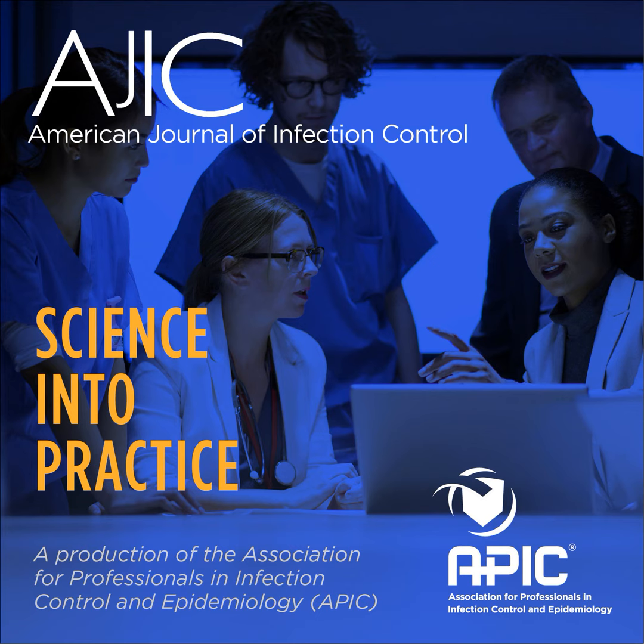Duodenoscope reprocessing is a complex process that includes so many different steps. First there's pre-cleaning to remove soil, leak testing, and visual inspection, then a manual cleaning step, rinsing out the cleaning agents, and then high-level disinfection and alcohol flush. You can do that by an endoscope reprocessor device, or you can do sterilization with ethylene oxide gas. Then you have to track that the scope has been sent through that high-level disinfection, dry the scope, and then store it in a specialized cabinet that keeps it clean and ready for use. This usually adds up to over 100 individual tasks, and if any one part of this process is done incorrectly, or if steps are skipped, patients can be at risk.